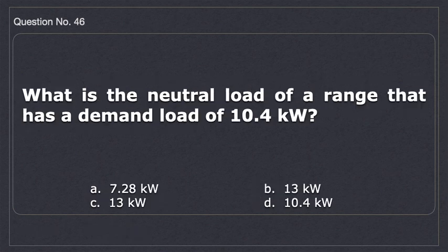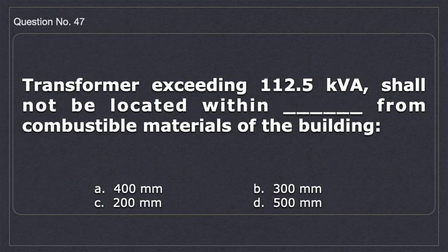Question number 46. What is the neutral load of a range that has a demand load of 10.4 kilowatts? A. 7.28 kilowatts. B. 13.5 kilowatts. C. 13 kilowatts. D. 10.4 kilowatts. Answer A. 7.28 kilowatts.